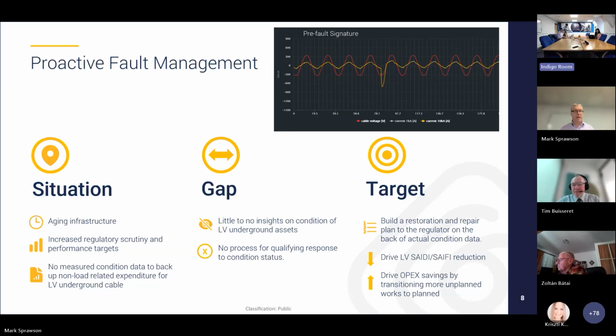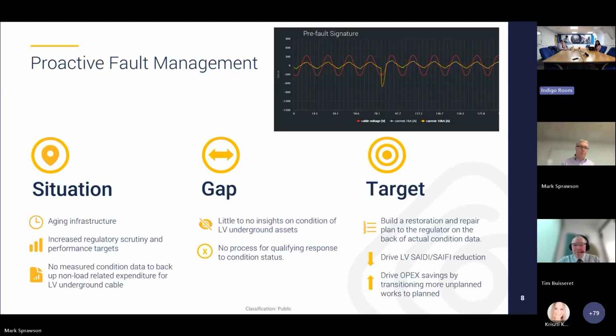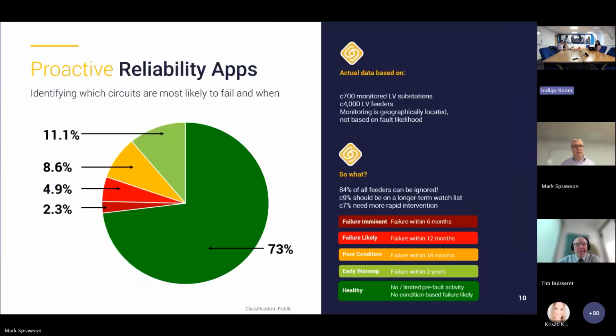So what we're seeing in the UK, again, is DSOs moving towards a pre-fault way of operating to try and actually fix faults before they happen and realize savings as a consequence. So how can you do this? Again, some example data here from some Grid Edge Intelligence. This data is taken from a fleet which is all installed in one geographic area. There are around about 700 substations there which are monitored, which equates to around about 4,000 low voltage circuits.